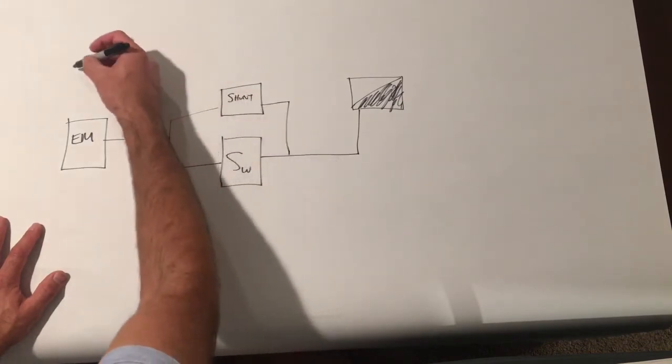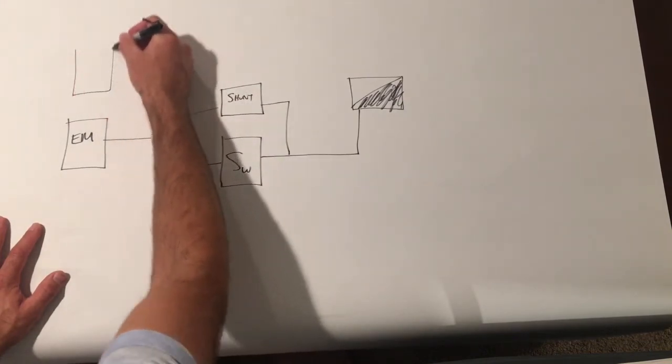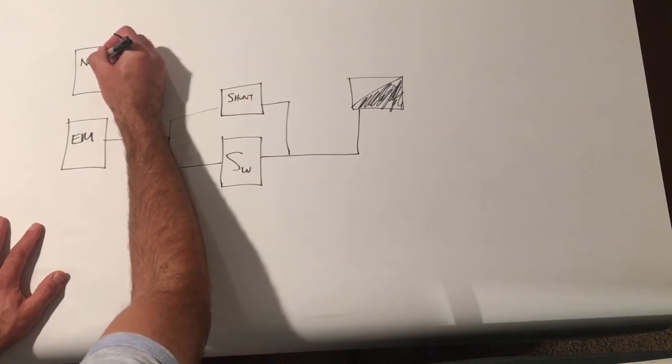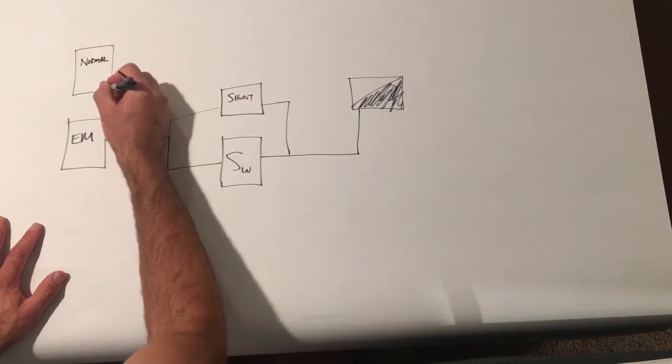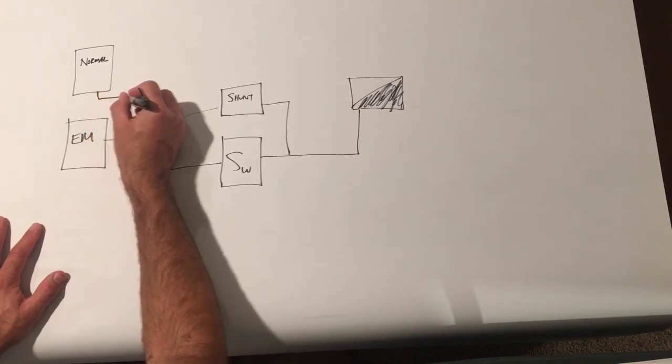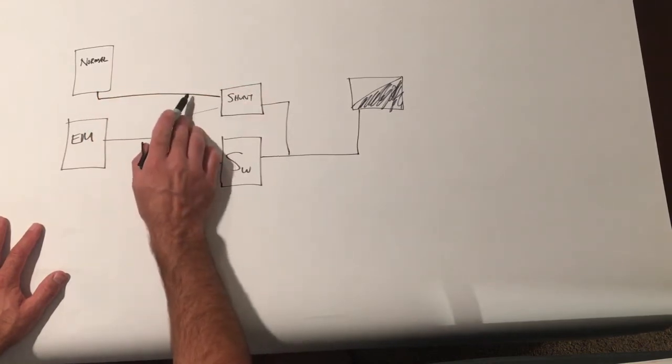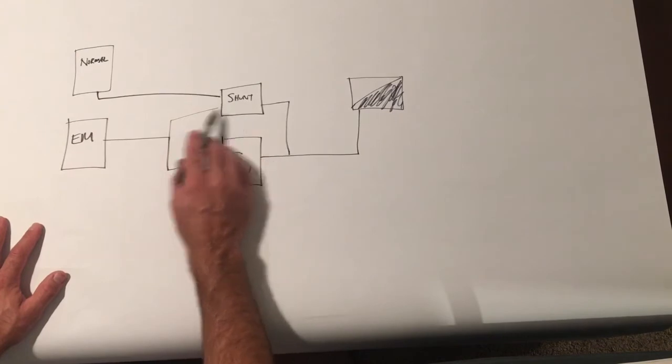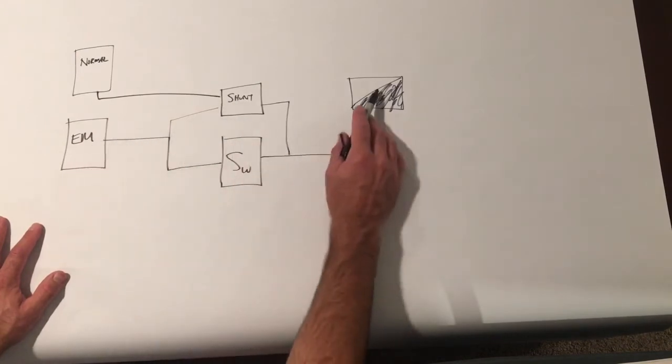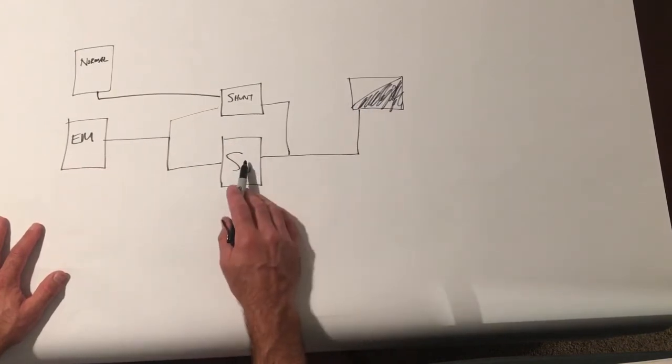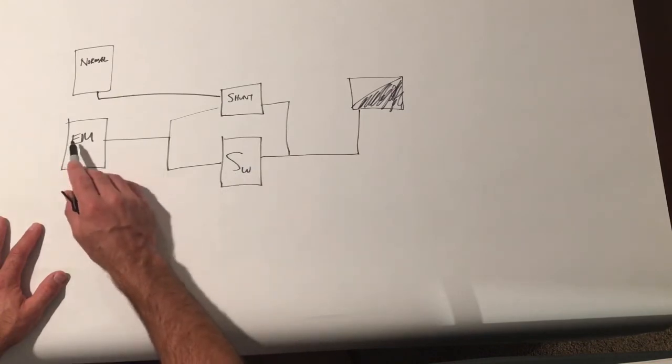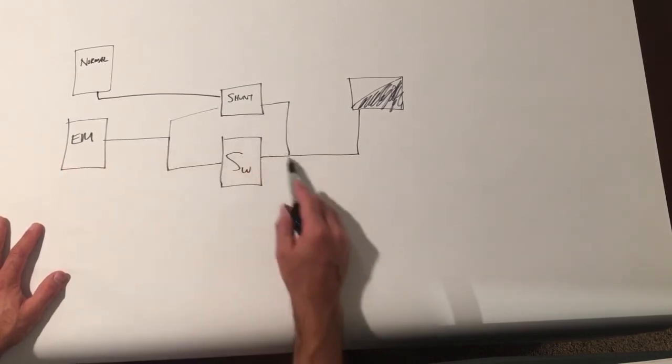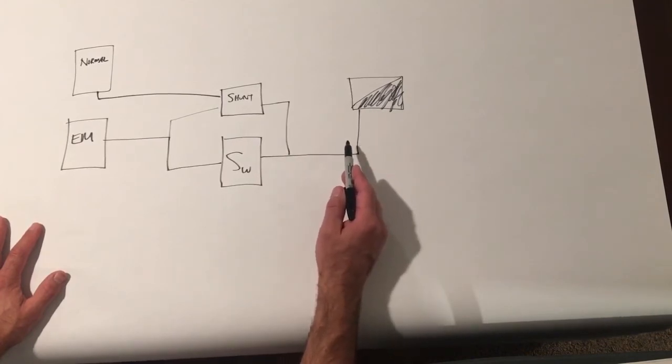We need one additional thing to make this work. So we're going to show our normal panel here, and we're going to show unswitched hot in there. So if we lose power, shunt relay closes, this light comes on regardless of the switch position. Again, the power flows through here and through here. So it's easy and it works well.